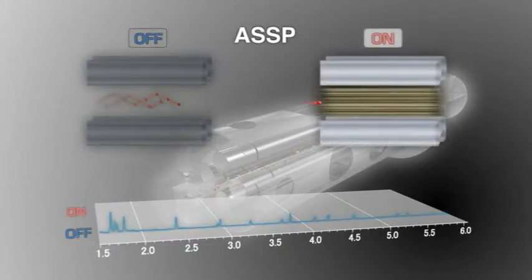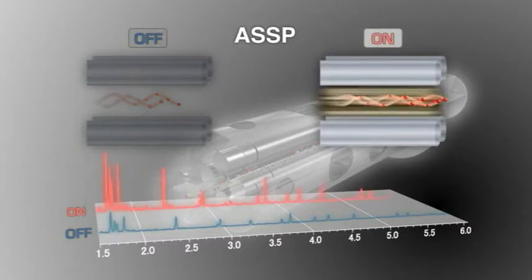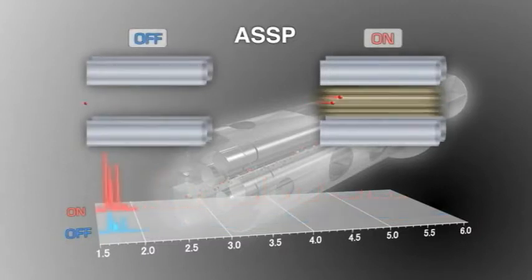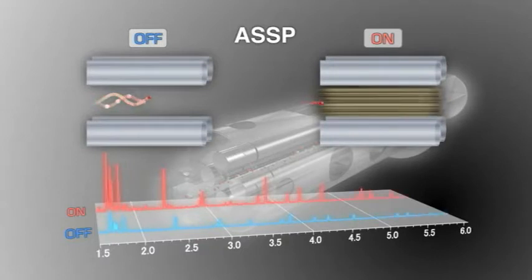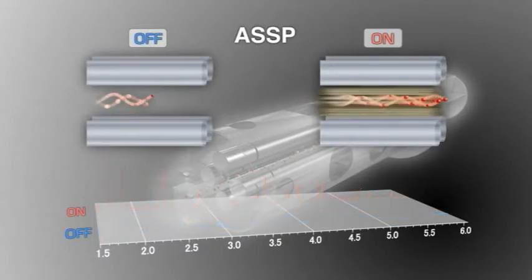ASSP automatically optimizes the rod bias voltage during ultra-high-speed data acquisition, thereby minimizing the drop in sensitivity and spectrum skewing that is normally associated with very fast scanning.